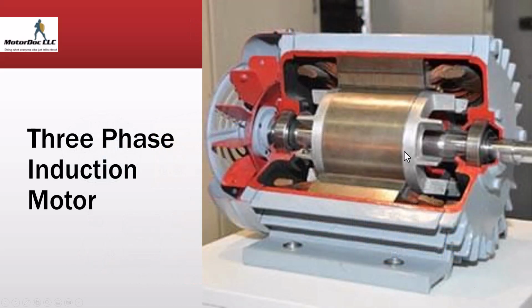So how it works is I use this machine here as the transducer when we're talking about a three-phase machine. So I have a shell that holds the bearing centered, so the rotor sits perfectly centered in the air gap, or as close as possible. There's laminations here, there's bars that pass through here. This is a cast aluminum, there's also cast copper, and then of course there is rotor bar style that'll have the bars come out in a ring that's separate from the core. There's other variations you'll see of the core, including venting in it and so on, but these are laminated so that you don't have certain losses in here. These will be thinner and of a higher grade of steel. The core is meant to hold the coils in place.